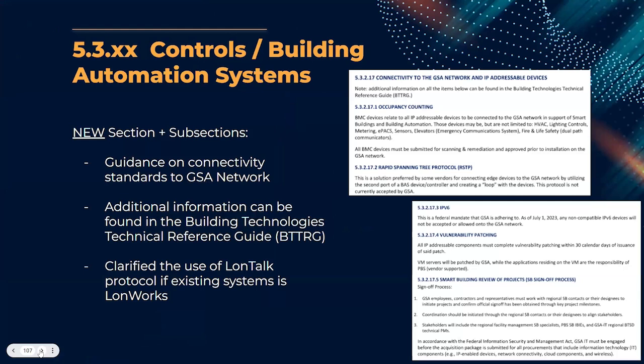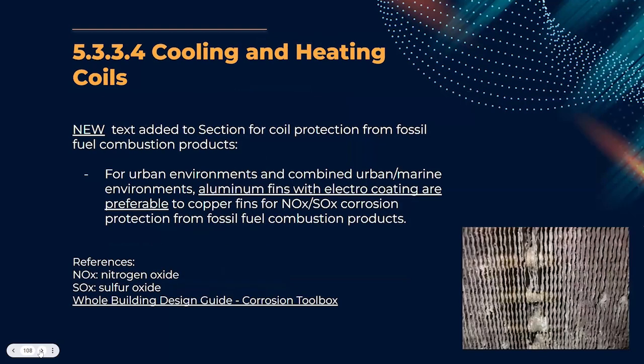There's also additional coordination language now clarifying coordination with GSA smart buildings personnel to ensure that those systems maintain consistency with the building automation standards that we provide. Next slide, please. We added additional guidance for equipment coils exposed to urban and marine environments to mitigate NOx and SOx corrosion. Some references have been provided, but essentially aluminum fins are required to have electrocoating, and are preferable to copper fins with NOx SOx coatings, for protection from fossil fuel combustion products for those lower intakes along a building's facade in an urban environment. Next slide, please.